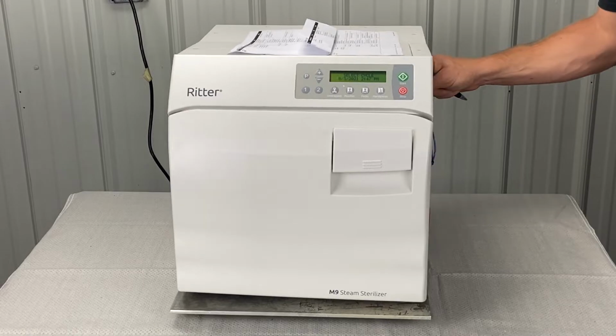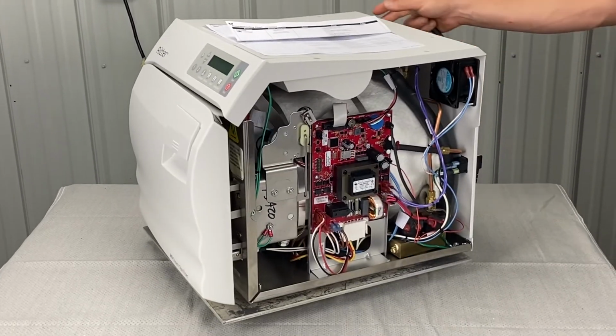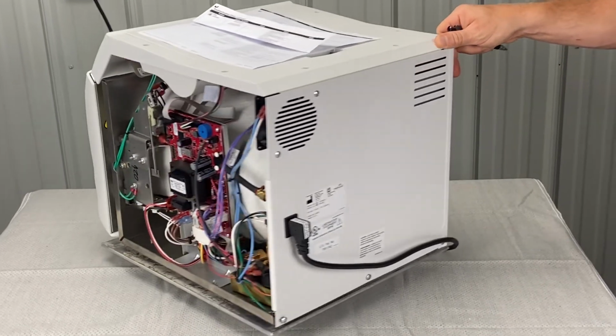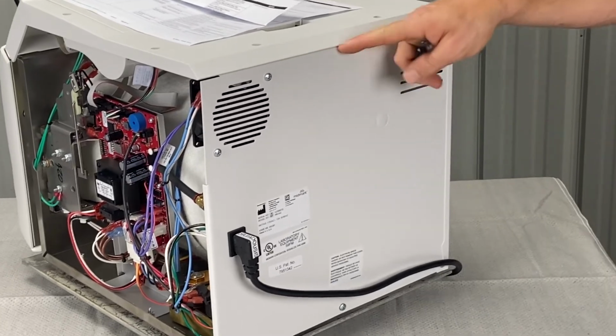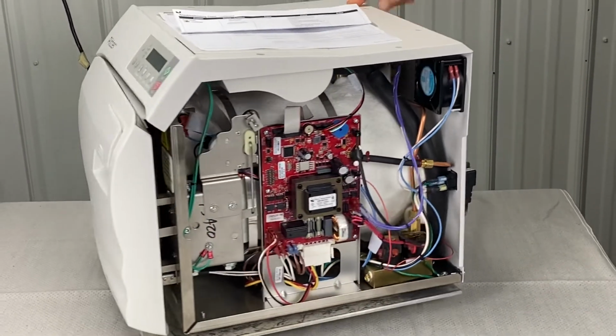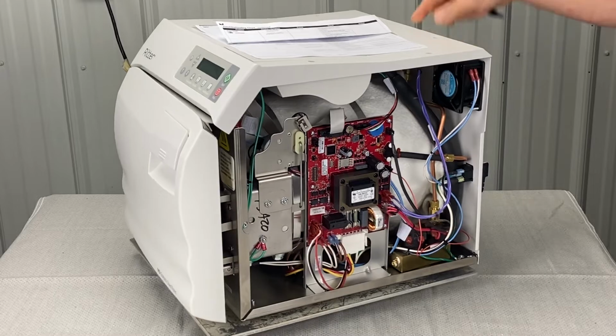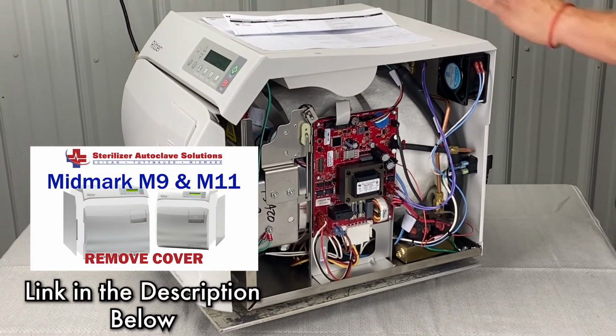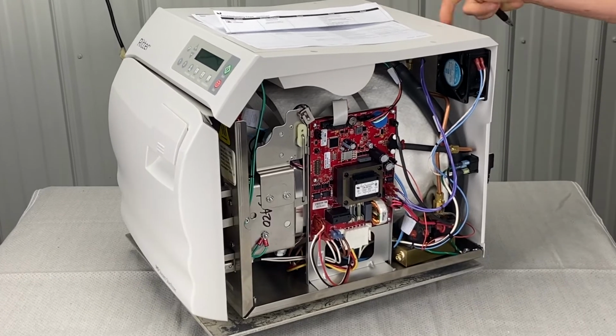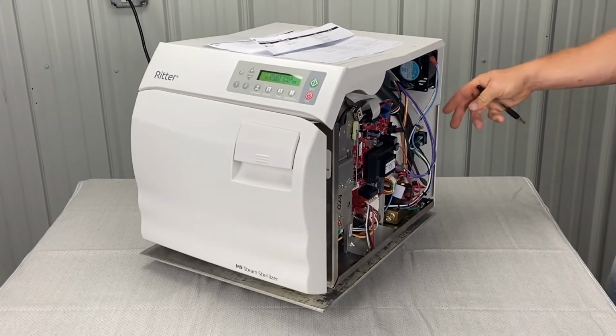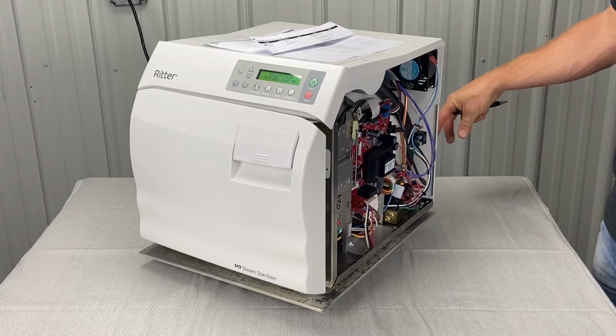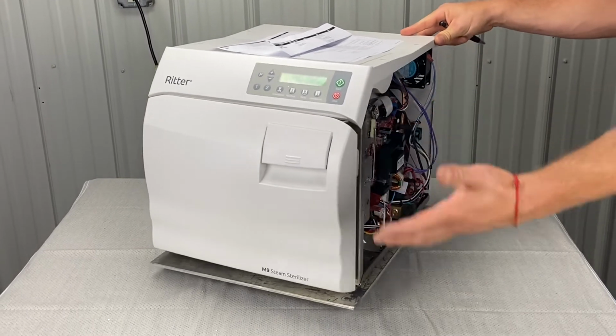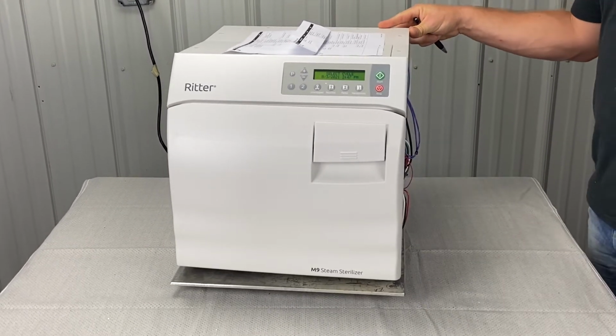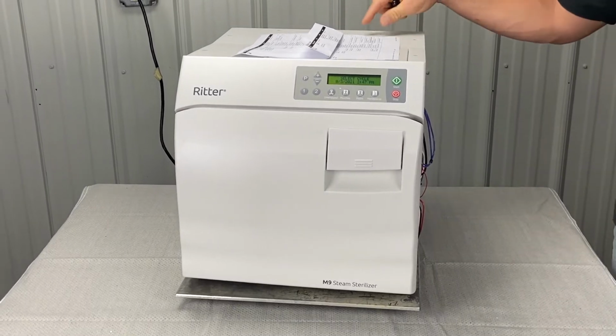Clean, replace air valve. Okay, so the air valve is all the way in the back here. You can't see it, but it's back here. So if we're going to go down this road, you're going to have to take the top cover off, side panel off, back panel off. This whole thing's going to have to come apart to inspect that air valve. Before you do that, you're going to unplug the power, drain all the water out, and then we can proceed.